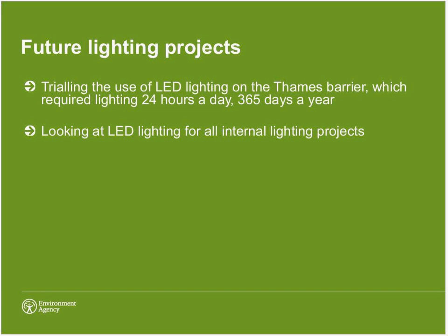They are a different kind of light to what they're used to, in terms of the warmer fluorescence that we tend to go for. But they found the colour quality really good. The standard should define what kind of colour rendering we should be looking for from the LED, so kind of 80+, and whether it will shift over life. So when we get the details from a particular LED lighting product, we can be confident that figure will keep us going for the extended life of the LED light.